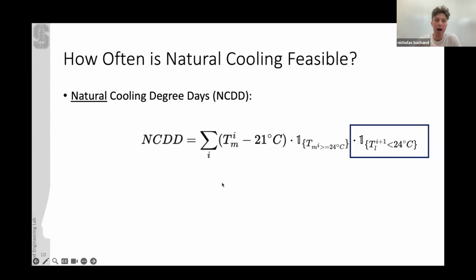If the nighttime temperature the subsequent day is very high, it's really infeasible to say that natural cooling is a solution, because no matter how much air we can drive through the building, we're never going to achieve this comfort temperature we're targeting. So this natural cooling degree day adds the condition that the subsequent low temperature should be below 24 degrees Celsius. So it's basically putting a condition on the nighttime low.